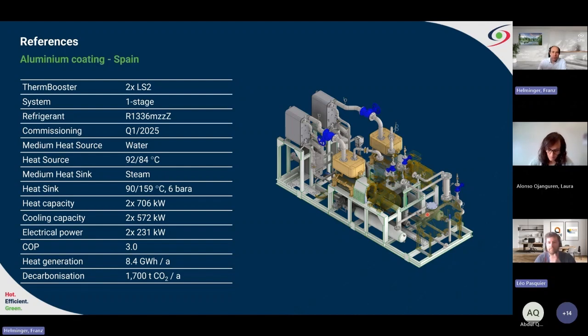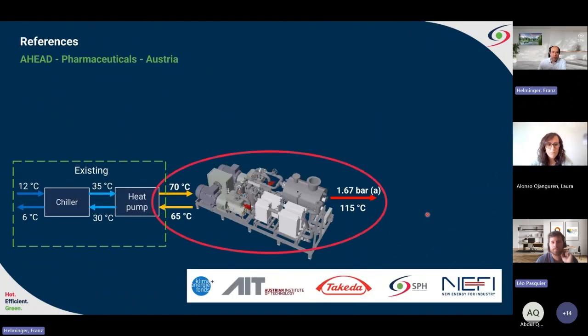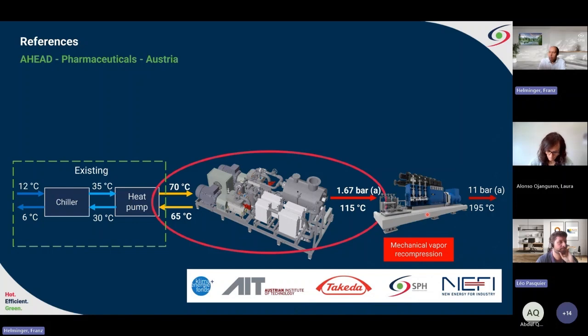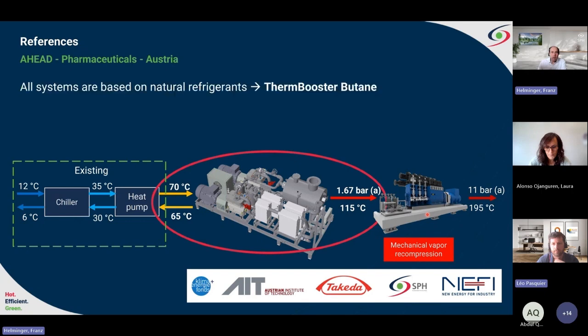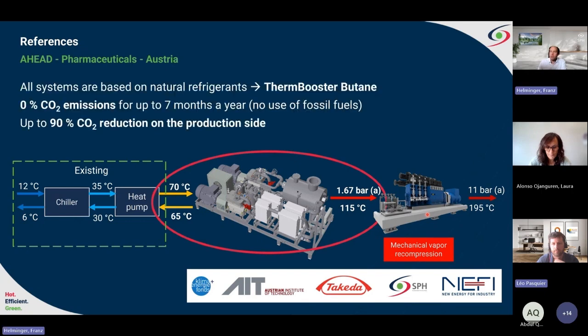Finally, just very short, I want to show you another project. It's a research project where we combine a steam generating heat pump from us, using butane as a refrigerant, generating steam of around 120 to 150 degrees C, and combine it in Vienna in Austria with a mechanical vapor recompression system to compress it up to 11 bars and 190, 195 degrees C at Takeda in Vienna. It's a natural refrigerant, as I said already, to generate steam and to go down to nearly 0% CO2 emissions for 7 months. As the heat source is not available the whole year, it's limited to around 7, nearly 8 months of the year.